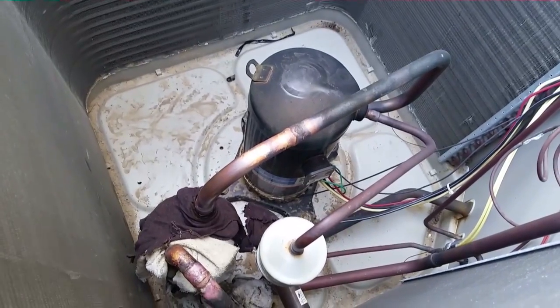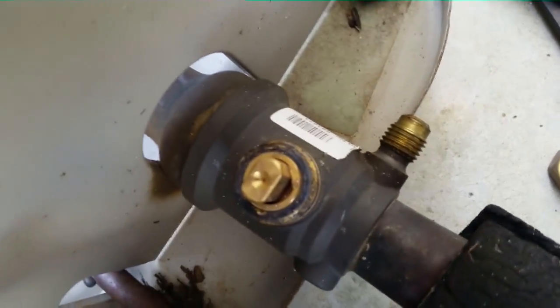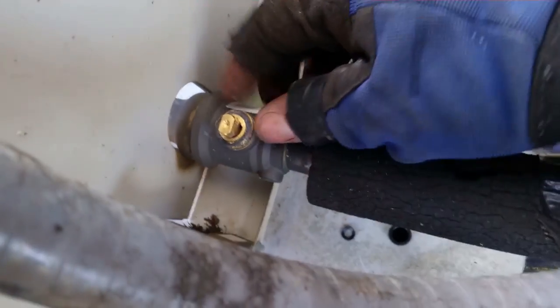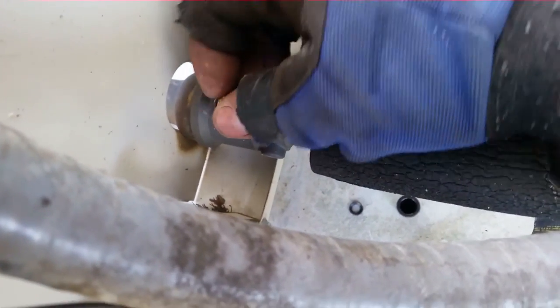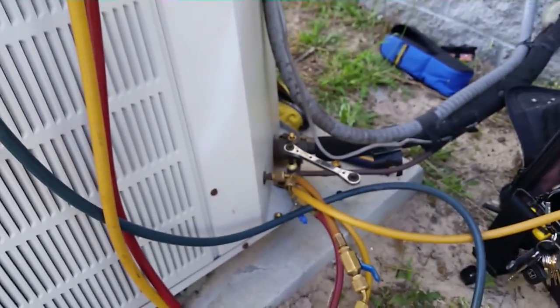I'll have my pressure test on. The new accumulator is all brazed up and looking beautiful. No leaks there — but wait. Service valve leaks on this Nordyne. Fantastic. Shall we say frustration?